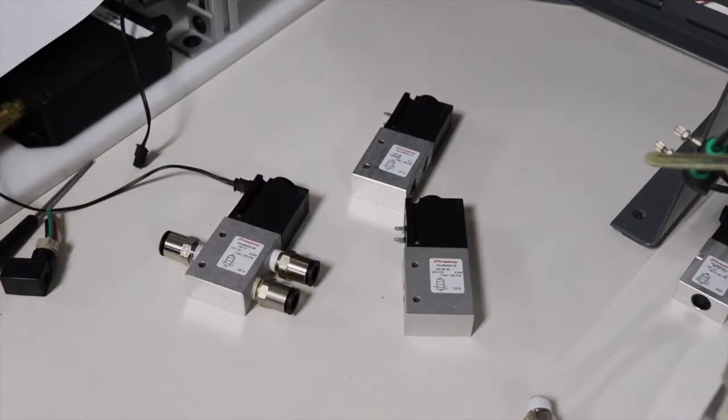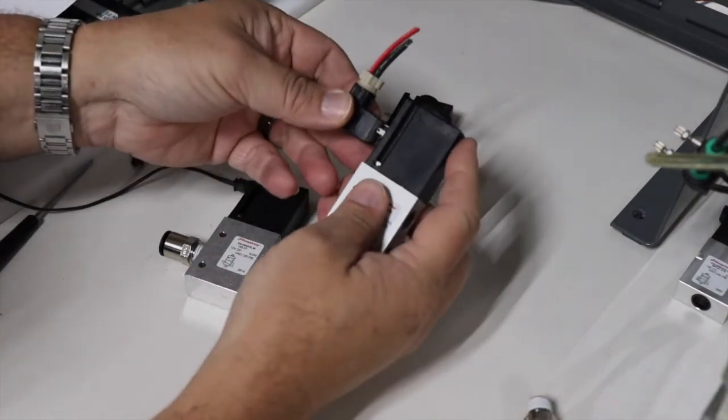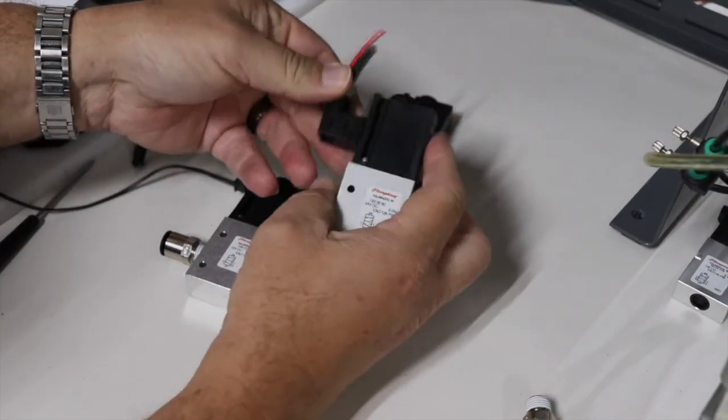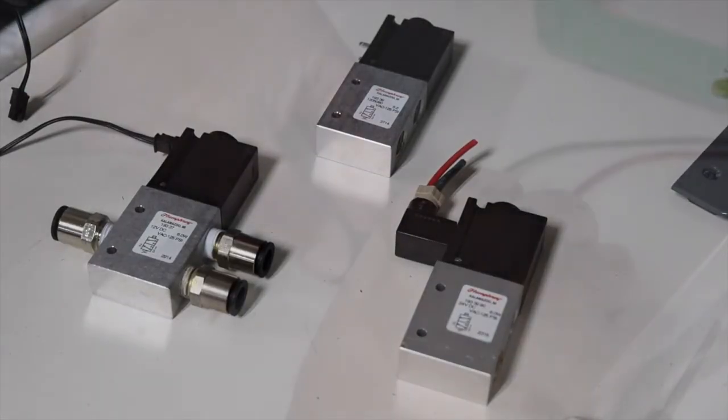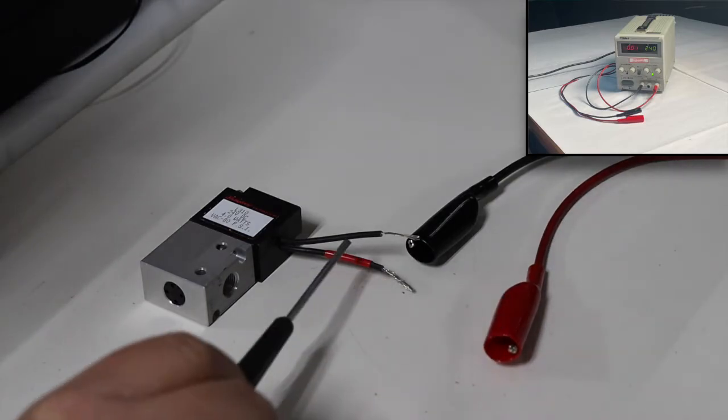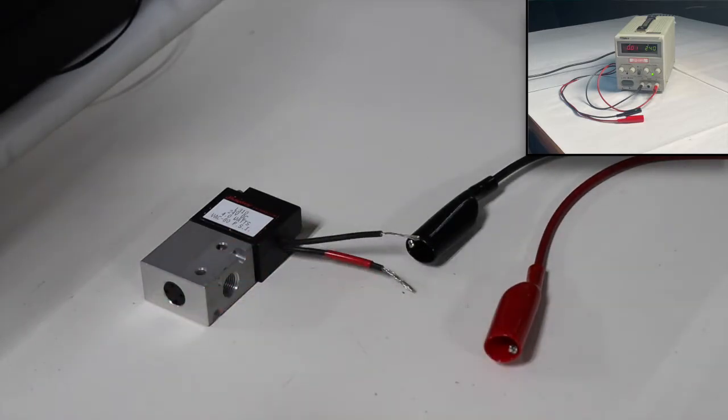Use the appropriate mating connector to ensure a proper connection. When connecting a valve, make sure you understand if your valve is polarity sensitive. If so, keep positive to positive and negative to negative when installing the valve.